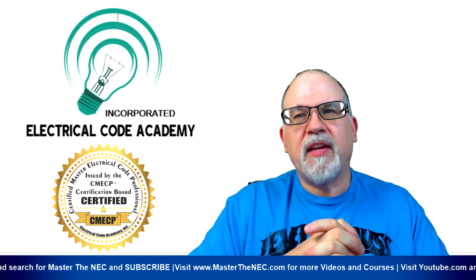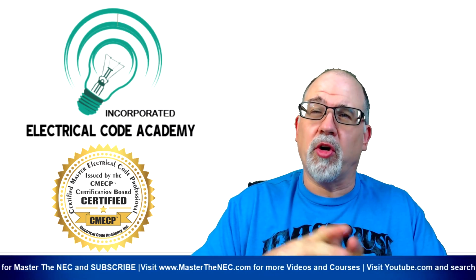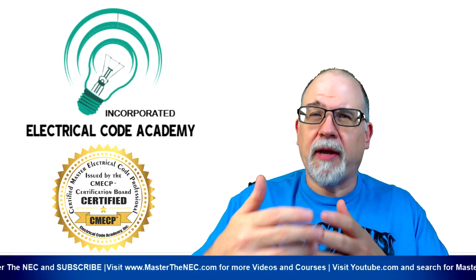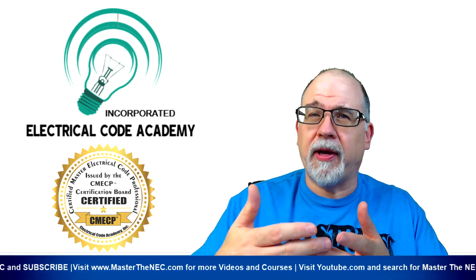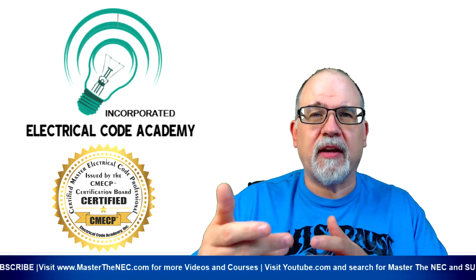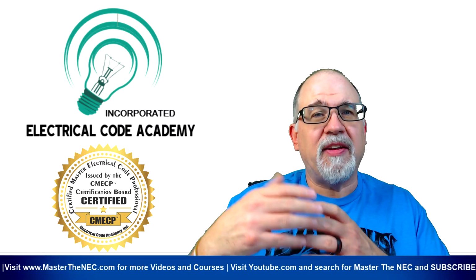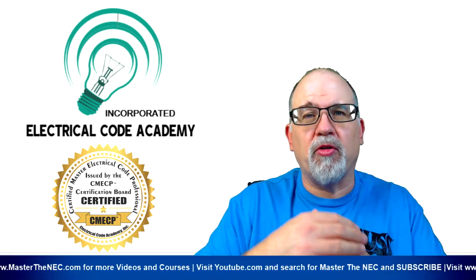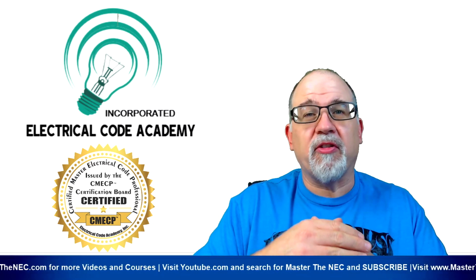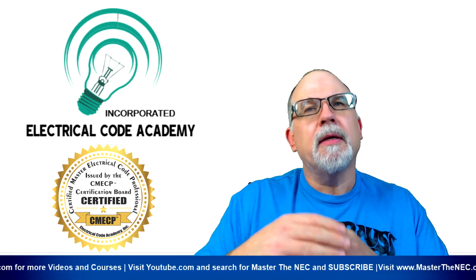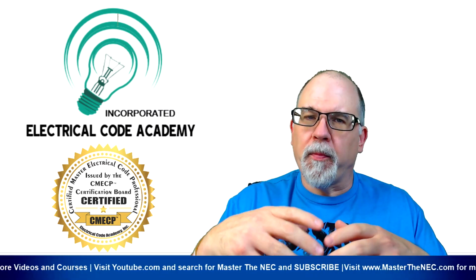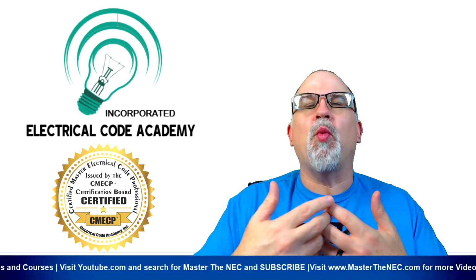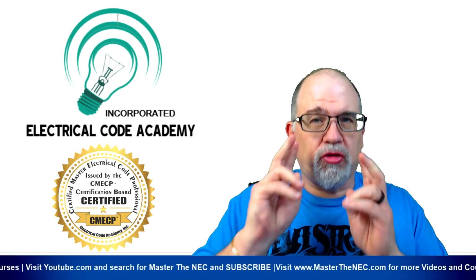Well, typically it's not going to be an issue because you're going to usually go into a panelboard, and the panelboard is required to have protection in 408.36. Those secondary conductors are going to be sized based on terminating into those overcurrent devices, based on the secondary conductor rules and whatnot. But for practical purposes, let's talk about when I don't need secondary protection of a transformer.